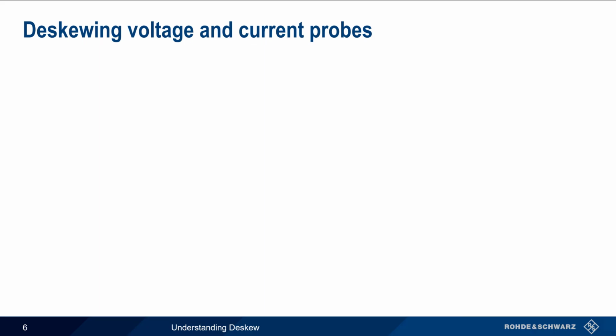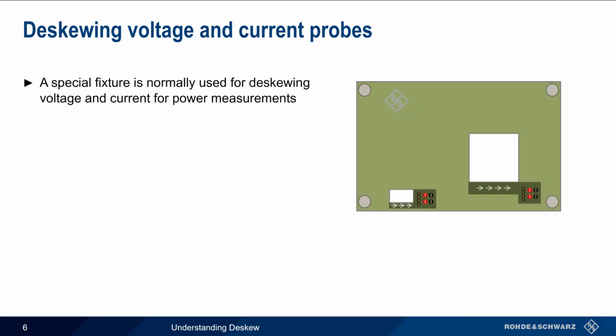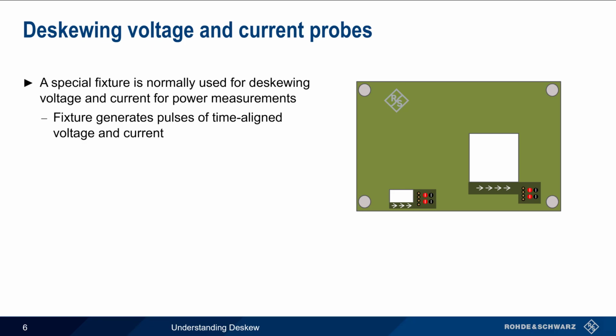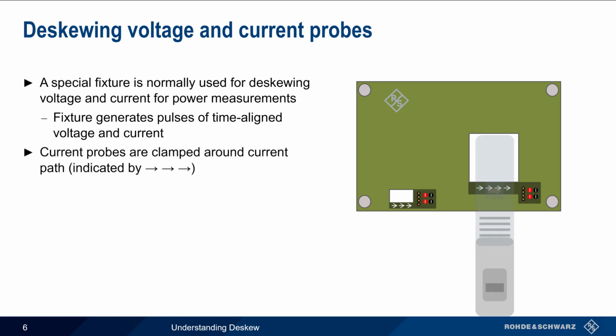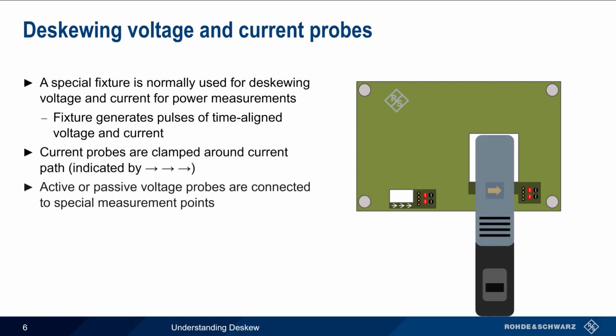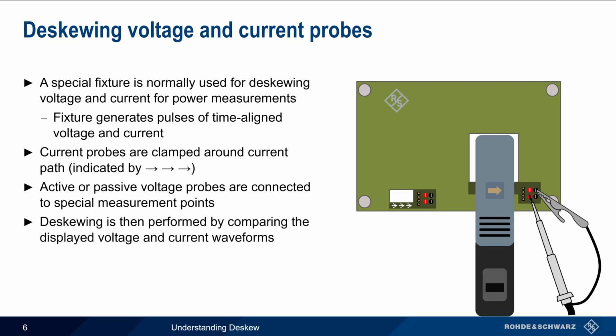When de-skewing a combination of voltage and current probes for power measurements, a special de-skewing fixture is normally required. This fixture generates time-aligned voltage and current pulses. A current probe is clamped around one of the current paths on the board, and either active or passive voltage probes are then connected to special measurement points next to the current probe connection. De-skewing is performed by comparing the displayed voltage and current waveforms and adjusting the skew on one or both channels until the voltage and current waveforms overlap.